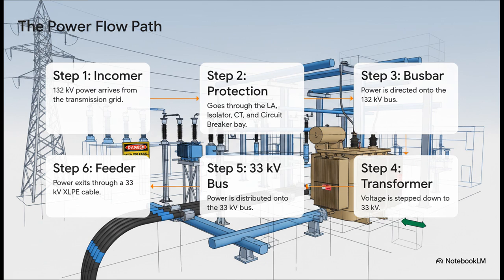Power comes in hot at 132,000 volts. Right away, it hits a bay of protective gear before it even gets to the main 132 kV bus bar. That's kind of like the central distribution hub. From there, it's directed into the massive power transformer, which does the heavy lifting, stepping it down to 33,000 volts. Finally, it hits another bus bar and gets sent out through underground feeder cables. That, in a nutshell, is the entire journey.